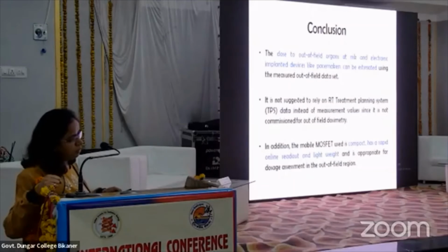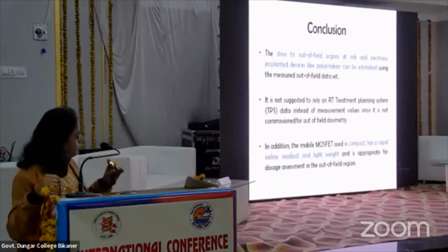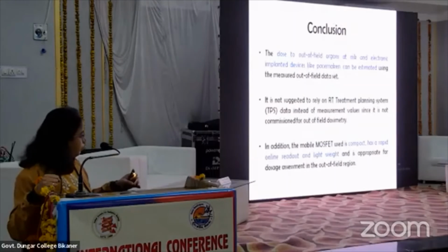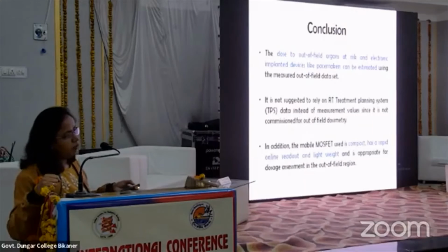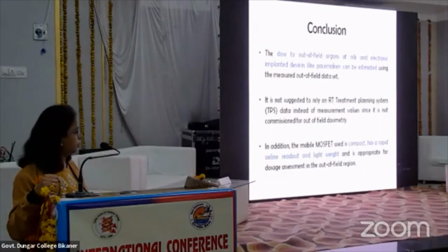The radiotherapy treatment planning system, we use it for the planning of radiotherapy patients. So that data can be relied on only for the in-field treatment volume, how much dose is going inside the treatment volume. But outside the treatment volume, how much dose is going, it is not exactly commissioned in the treatment planning system. So from the TPS, we cannot estimate exactly what is going outside the treatment volume.